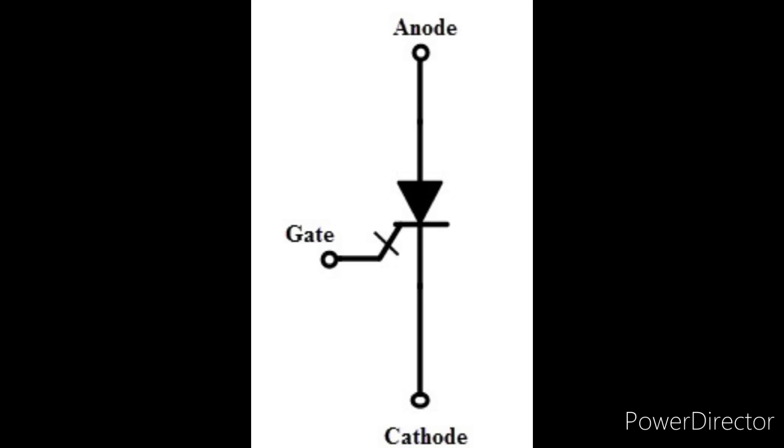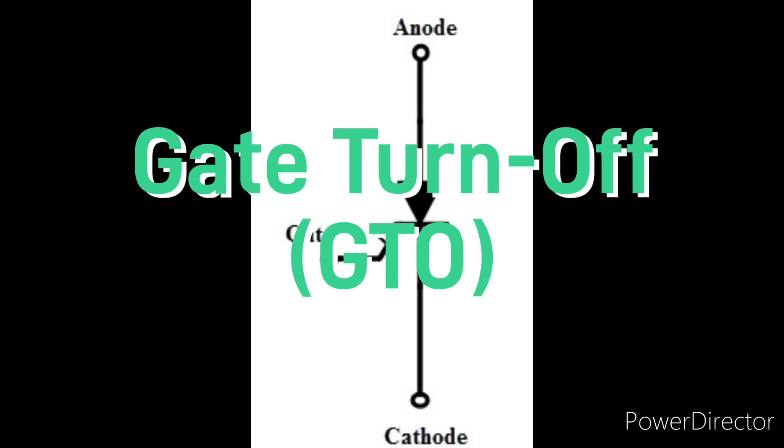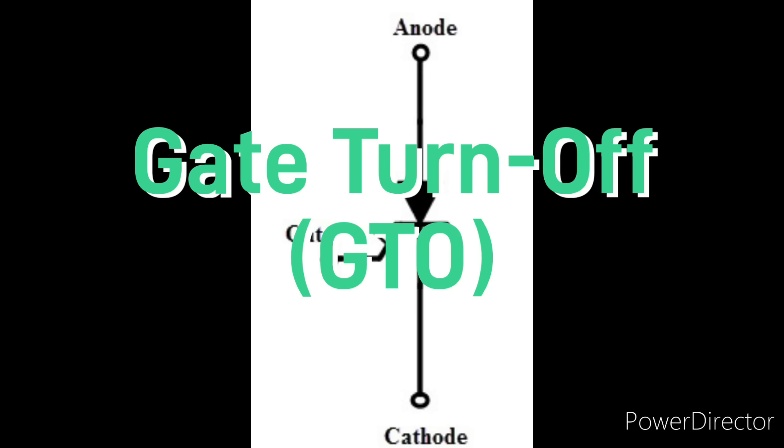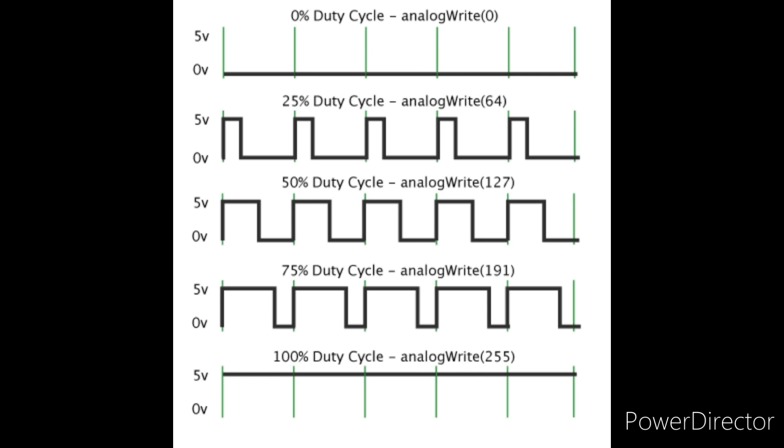Now in the mid 80s a solution was developed by using gate turn off or GTO thyristors. These are basically electronic switches which can either be on or off but never halfway. In order to control the current, the thyristor is switched on and off really quickly at a set frequency with the amount of on time being varied. The more on time, the higher the current.